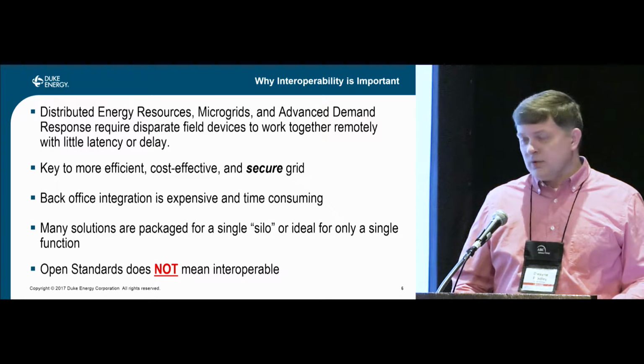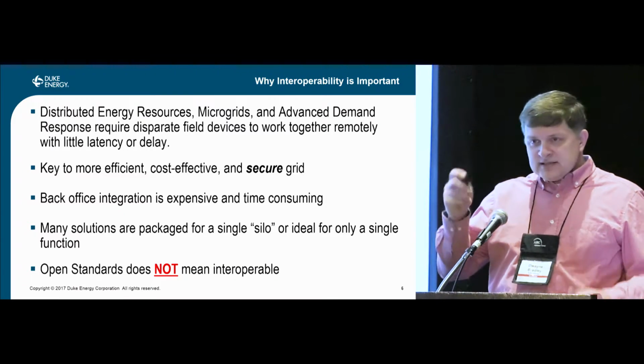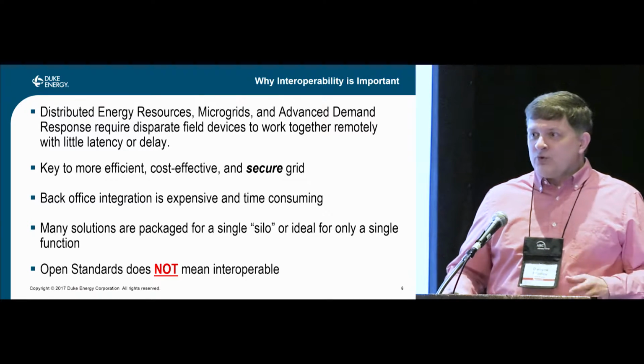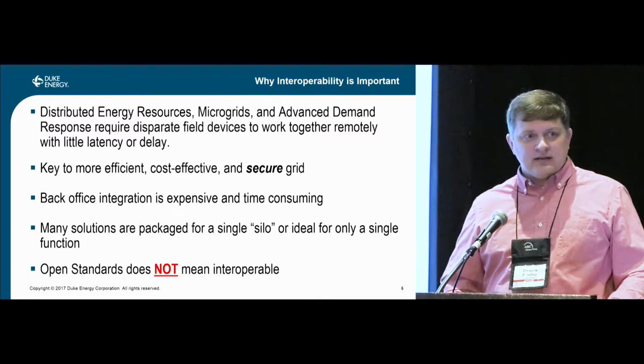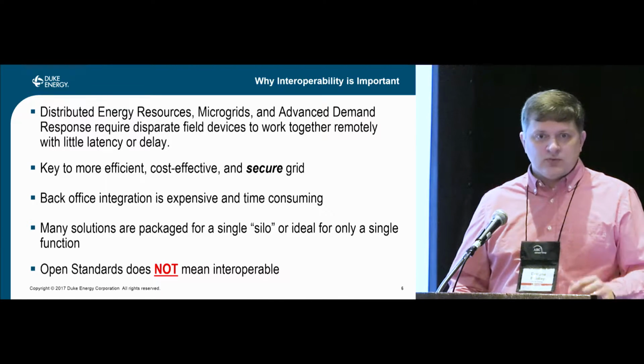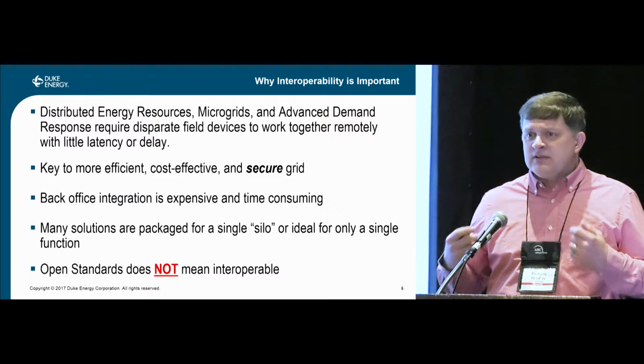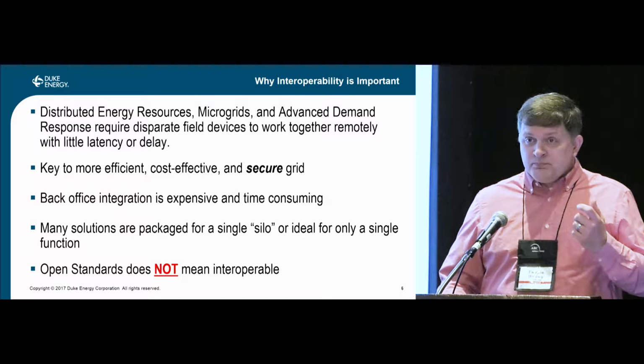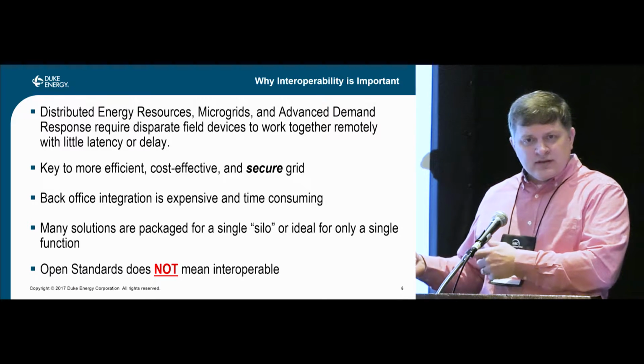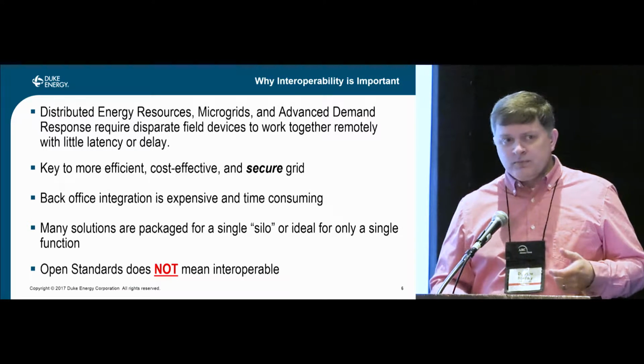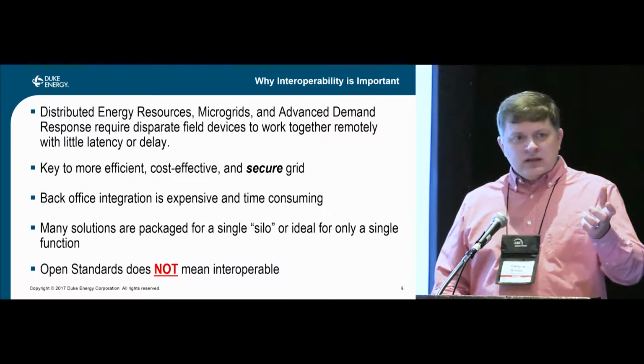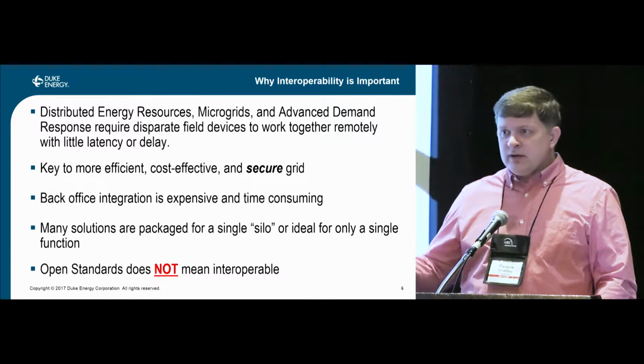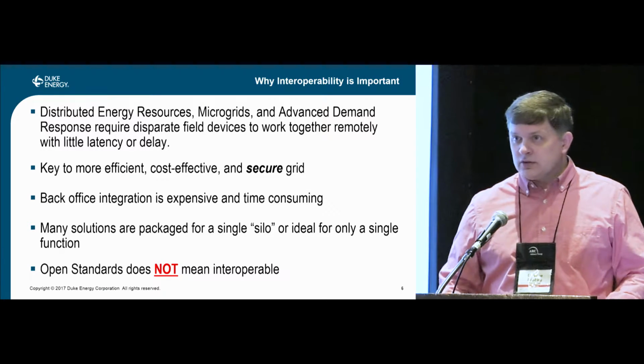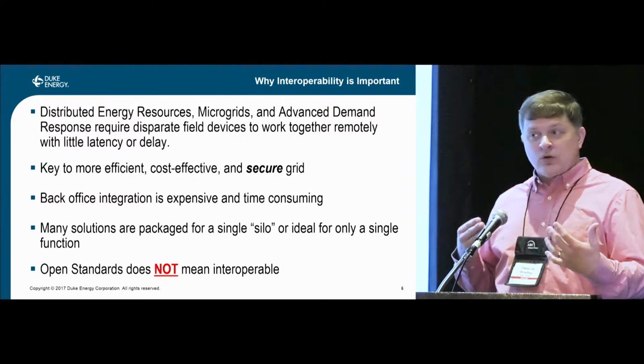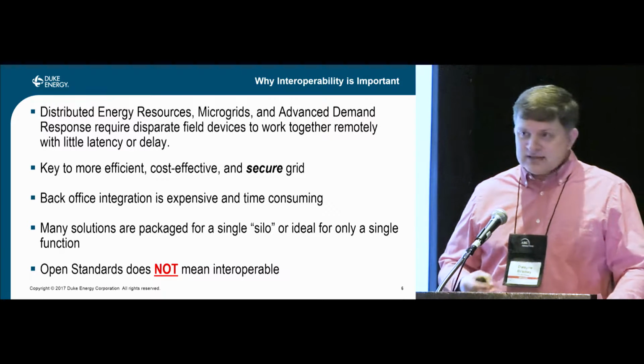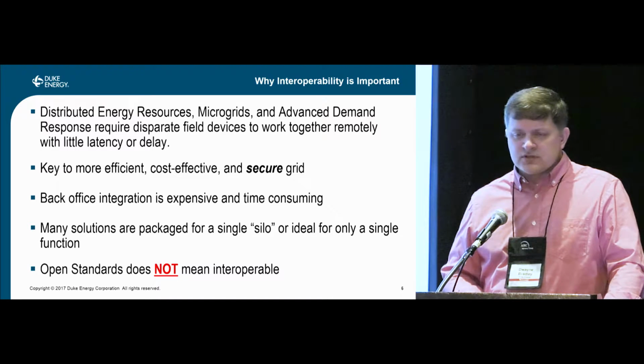Another thing we really ran into was that all the devices we were putting out in the field conformed to some open standard — whether DNP3, Modbus, C12 for meters, or 61850. They all conform to those standards, but that doesn't mean they're interoperable. I couldn't take a meter from one vendor, pull it out, put in a meter from another vendor, and expect it to work — they only worked within their own proprietary siloed systems. For us, that's just not a workable solution.